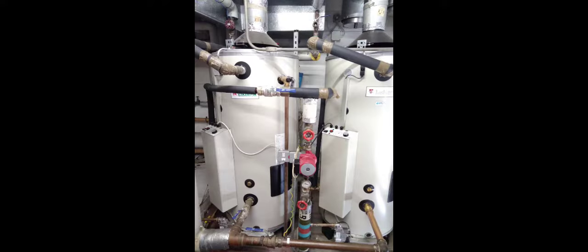Still in the process of wiring it up here. I believe I got it in situ and all was well. These are the units it was serving - two Lochinvar gas-fired water heaters. You could only have one on at a time, otherwise when two came on it would trip. That seemed to solve the problem - it looked as though the contactor was faulty.